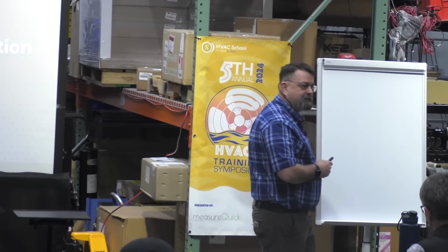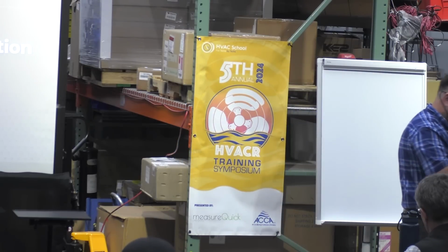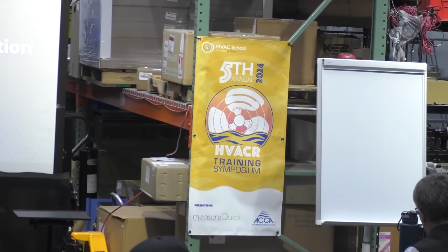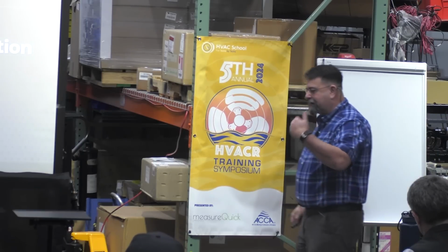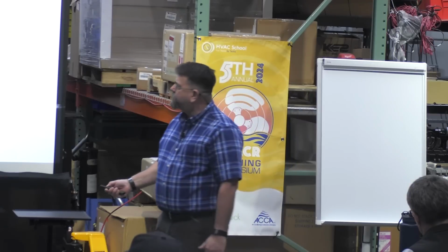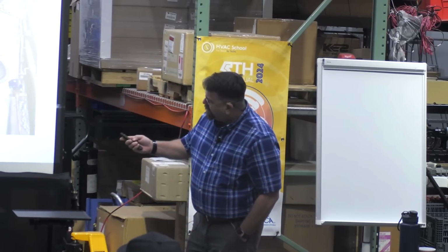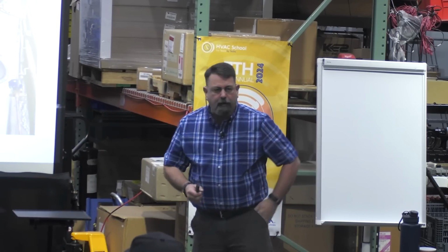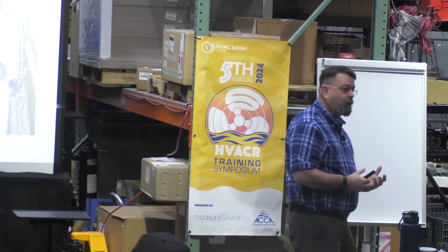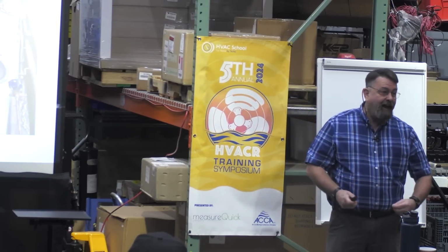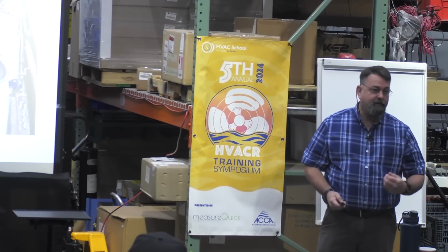Yeah. So I find it pretty fascinating that you have open cases that are 38 degrees, and I'm sure there's an engineered design of like a wind curtain that blocks that. Can you explain a little bit of the principle behind that? Yeah, right. So he's asking about that air curtain, and let me just back up to that drawing. It kind of shows it. There we go. So my air curtain is, I'm going to take about 50% of my airflow, and the airflow is going to be way less than air conditioning, way less.